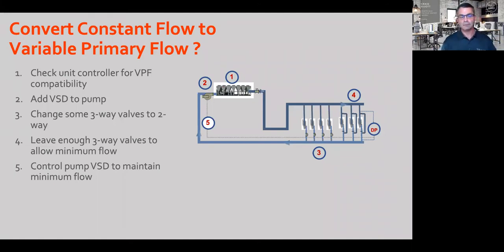There are a lot of constant flow systems installed in every geographic location. We refer to this as low-hanging fruit for retrofit. Follow the steps shown here to convert from a constant flow system to a variable primary flow. This works well in single chiller applications because of its simplicity. It also works very well in retrofit applications where a chiller is being replaced and the owner is interested in operational savings. Only some of the 3-way valves need to be changed to 2-way valves, with remaining valves acting as the bypass. A speed drive can be added to the pump, and you have a retrofit variable primary flow system that should be simple to operate.